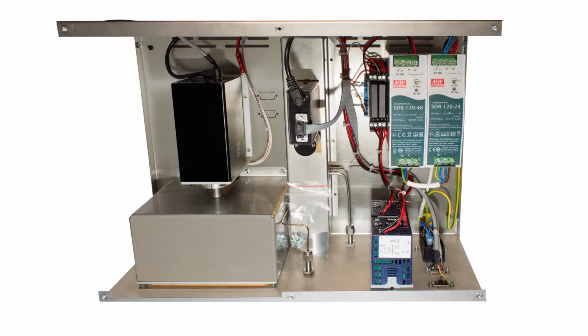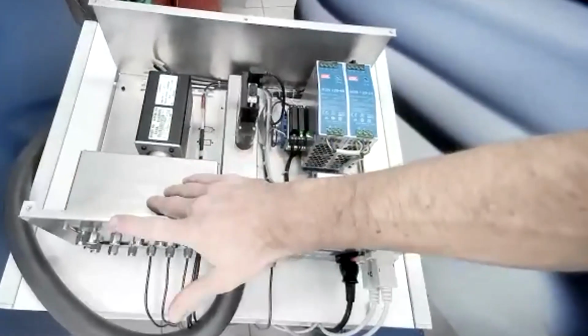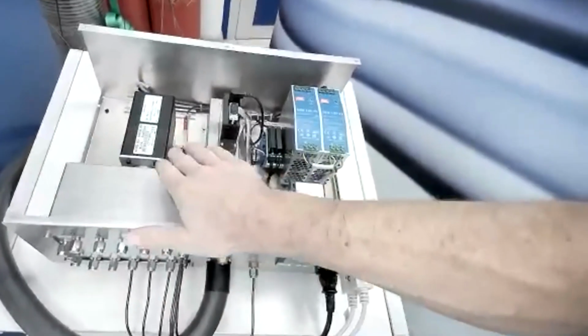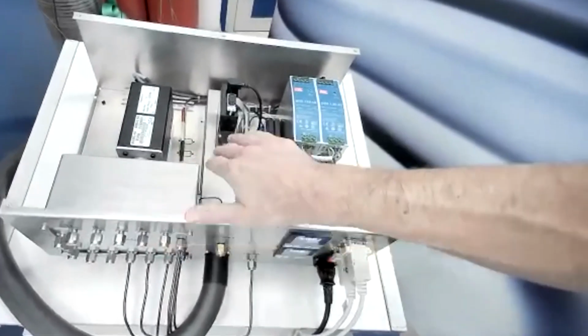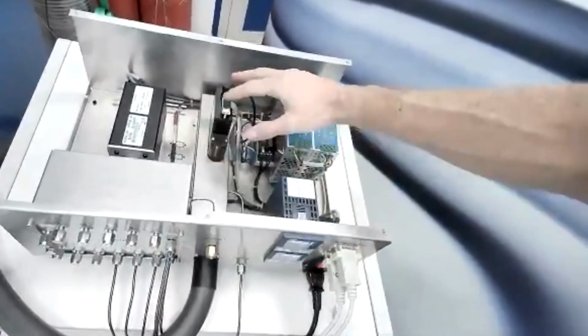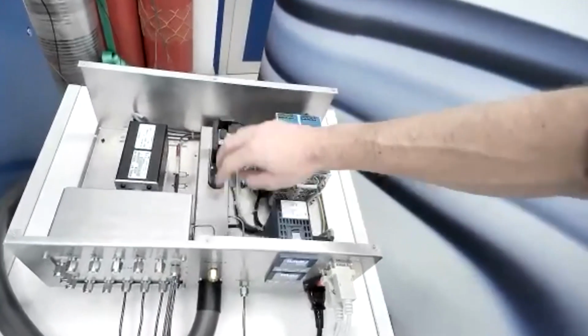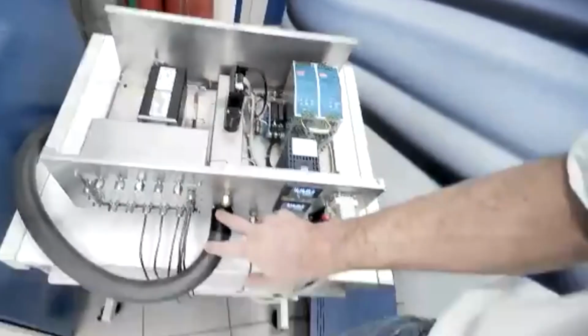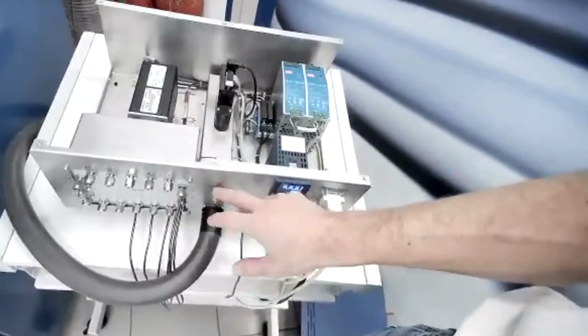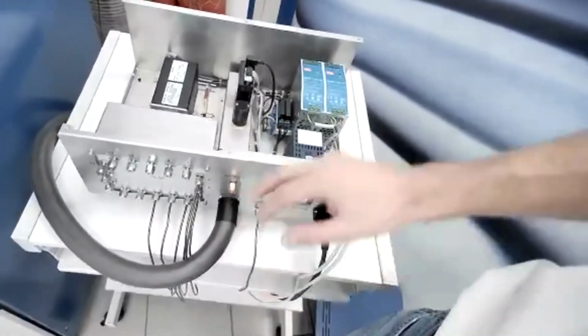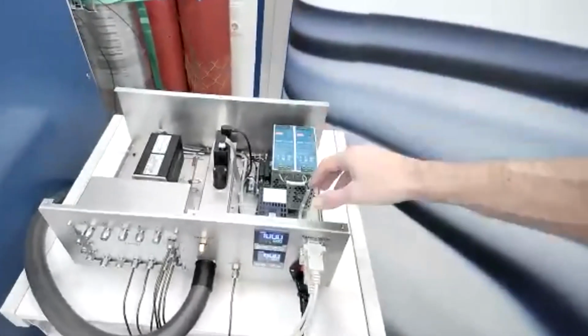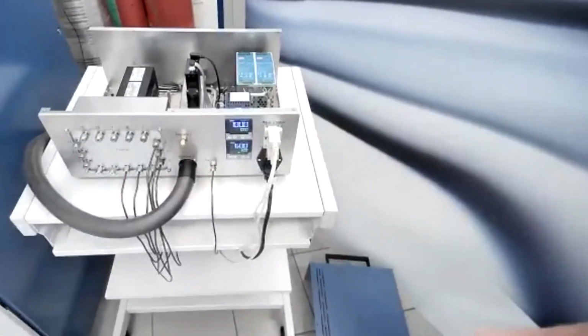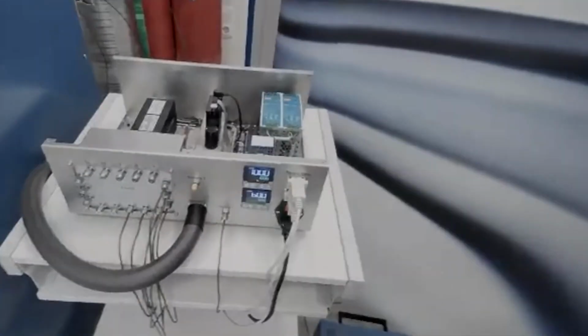So we can have a look inside. We're going here into this heated container. This is where all the lines will go to the multiplexing valve. Afterwards, we go through the mass flow controller, then provide the gas to the mass spectrometer and to the auxiliary devices. And then we have some power supplies, heating regulators and things inside in order to keep everything warm and to avoid any potential contaminants getting stuck in the multiplexing unit.